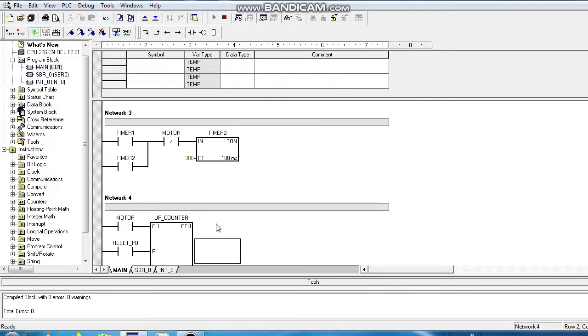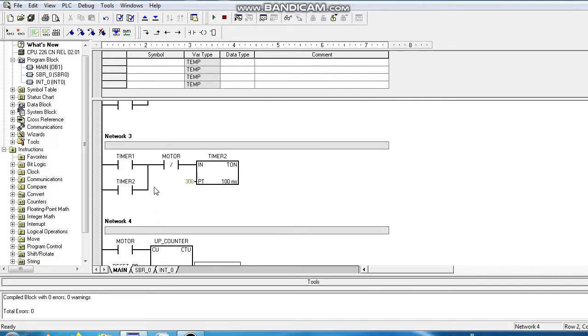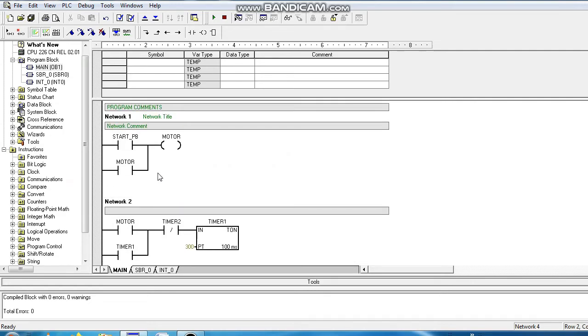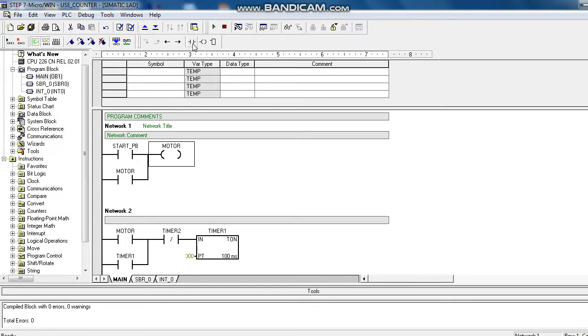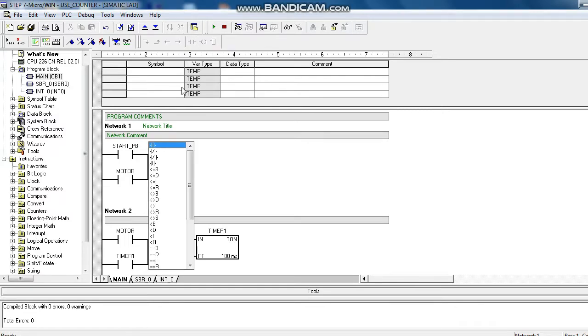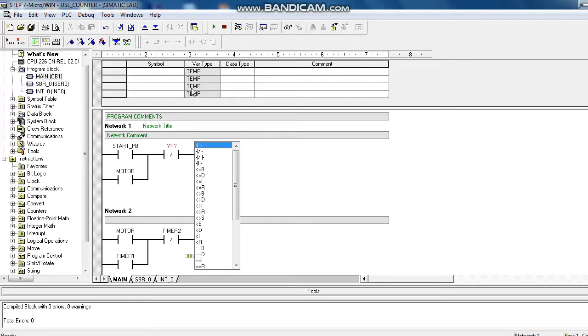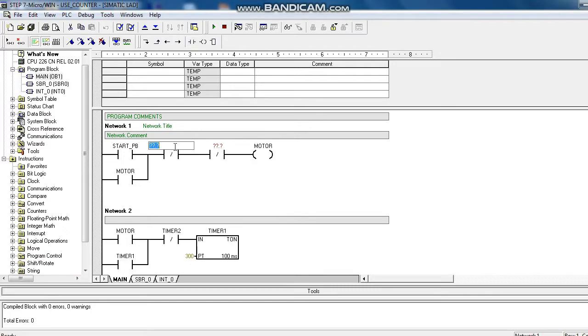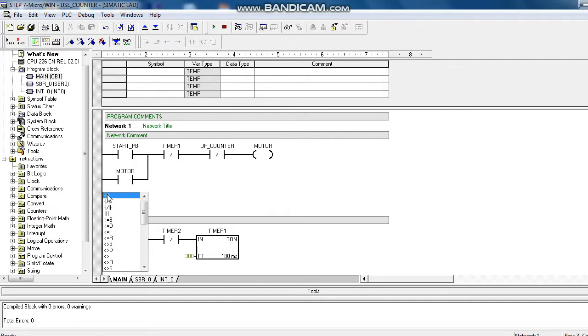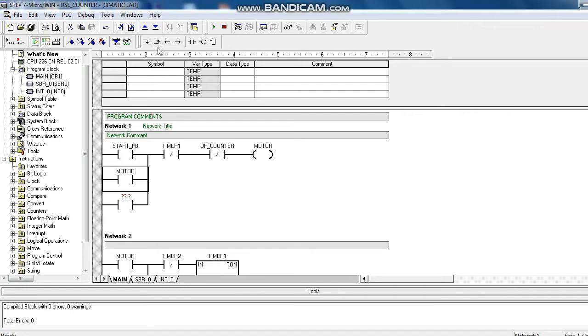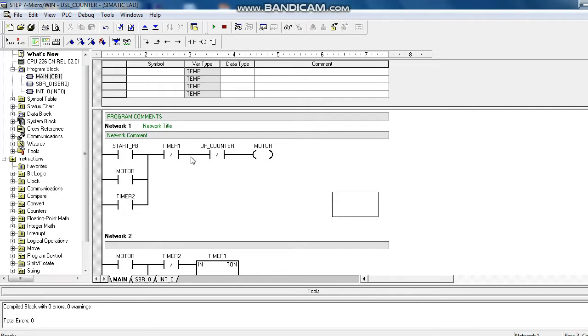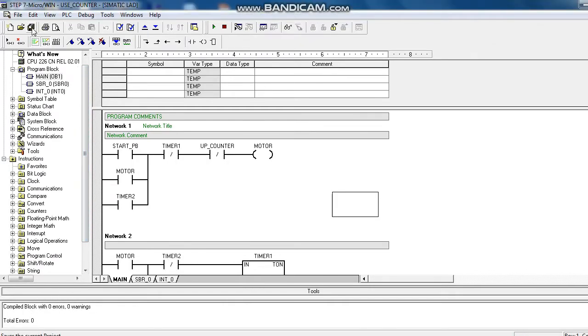Now when the counter is activated, we want to stop the sequence. So we have to use this contact in the motor circuit. Because when the timer is finished, when the counter is activated, this motor will be stopped. When the T37 timer is off, we want to again start this motor automatically. For we use the counter of timer contact of T38. Now here T37 will stop this motor, T38 will start this motor.